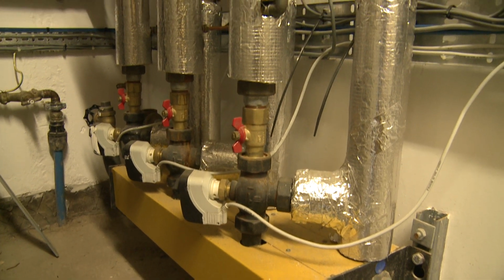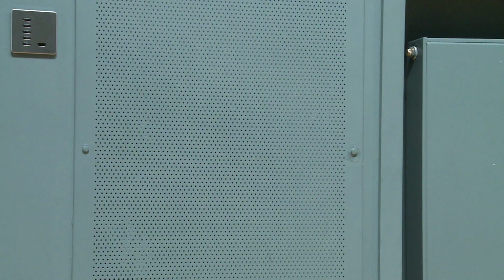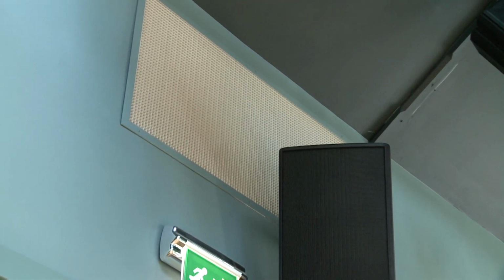The third use is in that same theatre. We have ventilation, necessary of course with 100 hot bodies, excited bodies. And in the middle of winter, when the cold air is pumped in to replace the hot air which is being extracted, first of all the cold air coming in is slightly warmed with a heat exchange with the hot air going out, but in midwinter that is not enough, so we have the facility to heat the air with hot water. And the fourth and final use is for hot water in the taps in the kitchen and in the toilets.